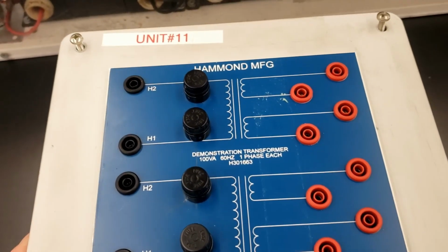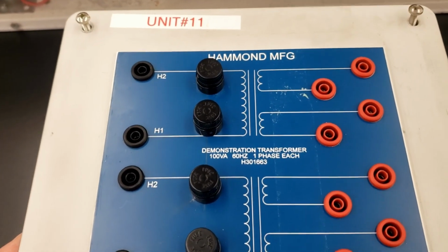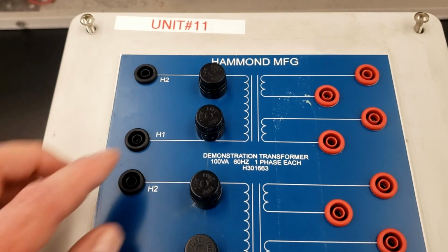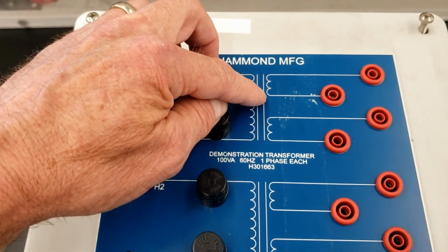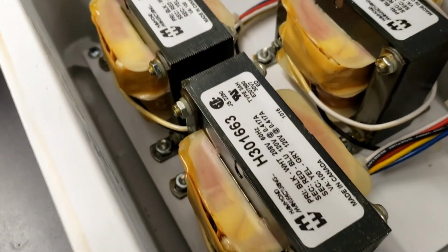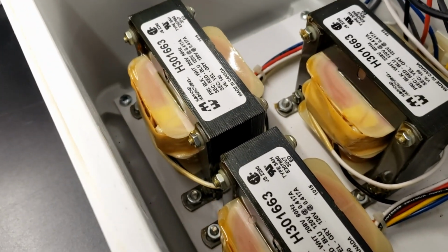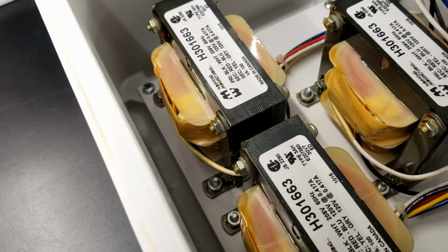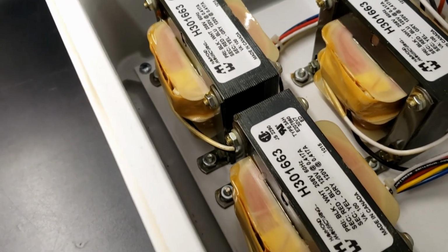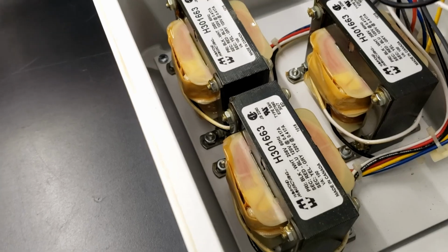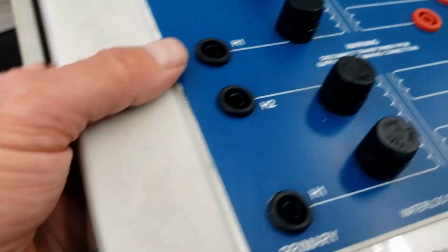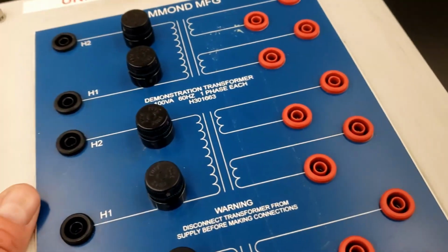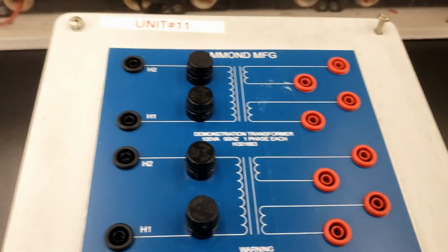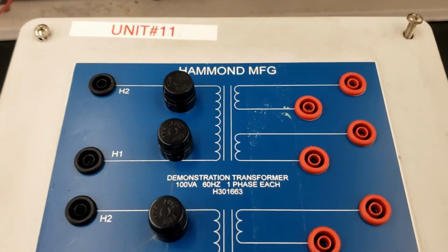So the next step is to check the resistance of the winding, to make sure everything's good with the actual transformer. Looking at the transformers, they look good. Nobody's actually cooked those windings, but we'll see with the resistance value whether the secondary and primary windings have identical resistances. Once we've confirmed the trainer is in good order, we're going to start doing a buck boost test.